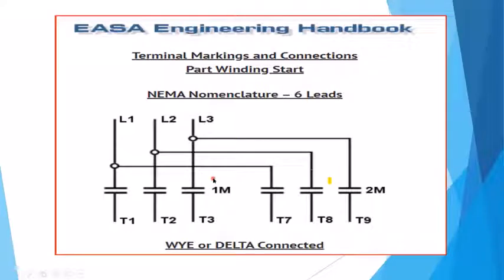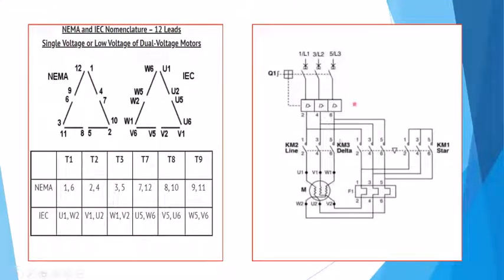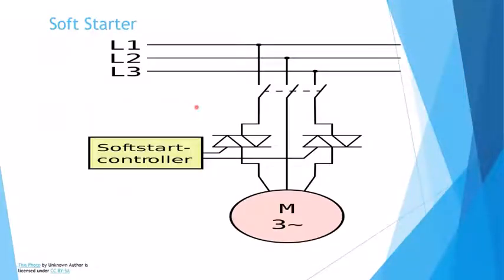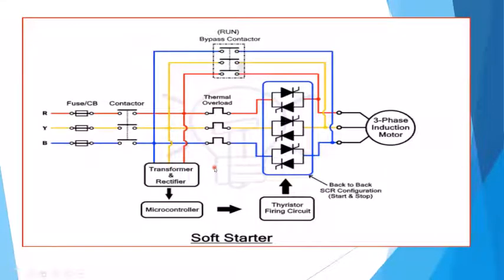Then they went to part winding start, which was also done back then. Then it went to where you put in half the winding and then the other half the winding. Then you also had the Y delta starters, where you basically connected. So you had 277 volts here first. And then when it was connected back to the line again. So it connected it out into a Y format out here, and then brought it back. And then you had, again, lowered the voltage to the winding as we started it, and it would end up basically cutting the inrush in about half. Then we had the soft starters, which were the thyristors, which we were basically turning on and off, controlling how much voltage gets to that motor, so we could really keep the currents down. So soft starters today, I think, are a pretty prime choice of what should be done if you take into consideration also a lot of the mechanics that are required.